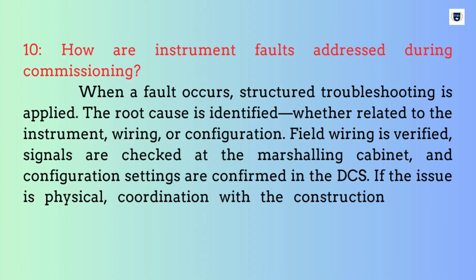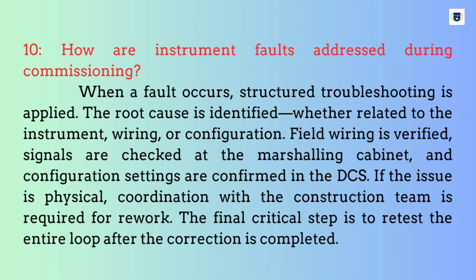How are instrument faults addressed during commissioning? When a fault occurs, structured troubleshooting is applied. The root cause is identified, whether related to the instrument, wiring, or configuration. Field wiring is verified, signals are checked at the marshalling cabinet, and configuration settings are confirmed in the DCS. If the issue is physical, coordination with the construction team is required for rework. The final critical step is to retest the entire loop after the correction is completed.